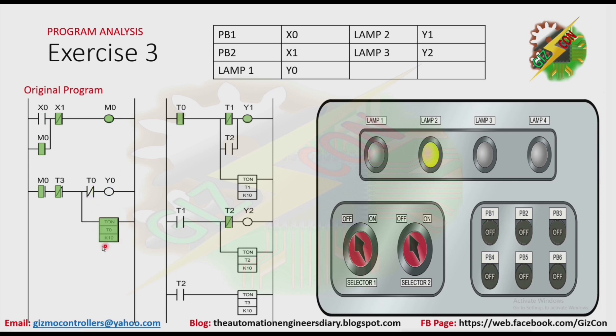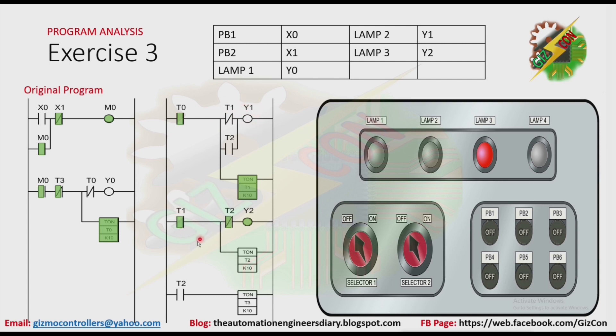Because T0 is activated, the normally closed contact of T0 here will open, and that will make Y0 to turn off. The normally open contact of T0 here will be closed — that will make Y1 to turn on. And T1 will be activated after one second. After T1 is activated, the normally closed contact here will open, making Y1 to turn off. Then the normally open contact of T1 here will be closed, making Y2 to turn on, and T2 here will be activated after one second.